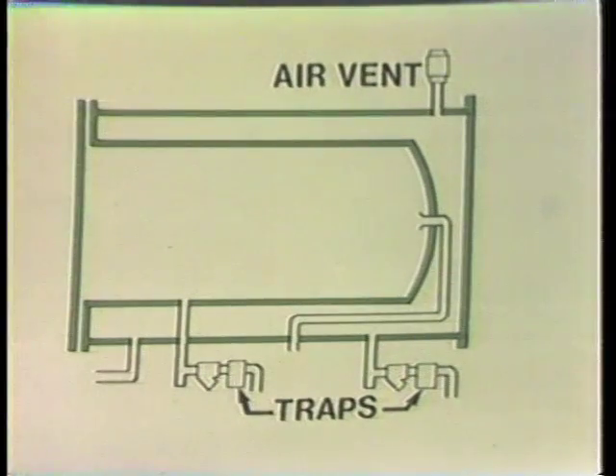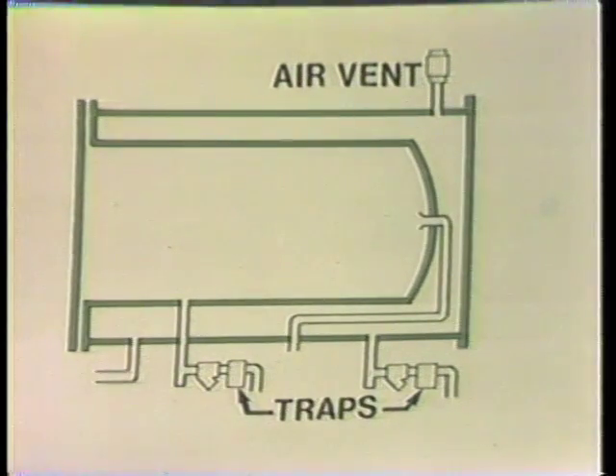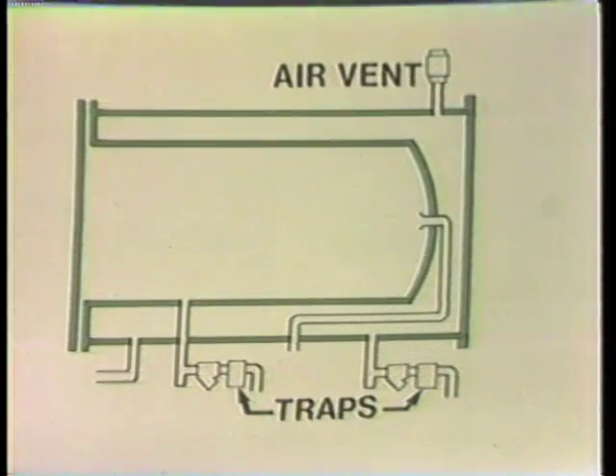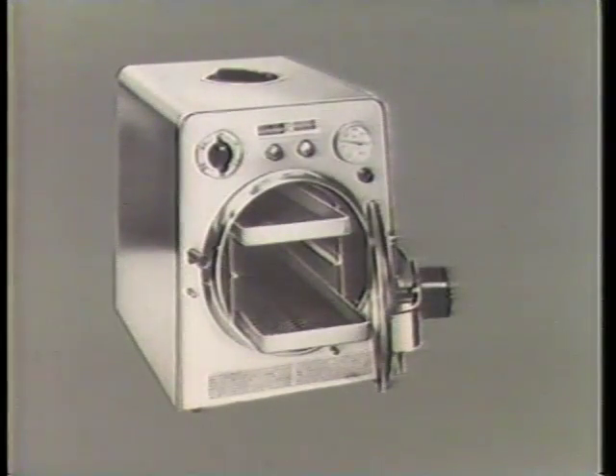This figure shows an autoclave used for sterilizing hospital instruments. The process requires that a temperature of 228 degrees Fahrenheit be maintained for a predetermined length of time. Normally, the required temperature can be reached by applying 20 pounds absolute to the steam inlet. However, if the steam is mixed with 25 percent air, the temperature would only reach 213 degrees Fahrenheit, and sterilization would not be assured.